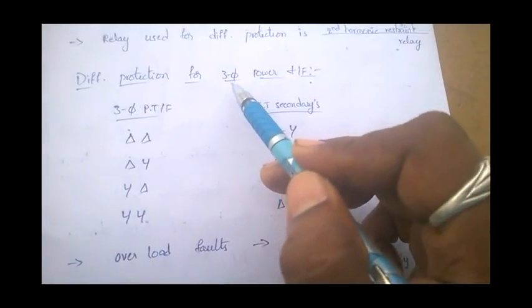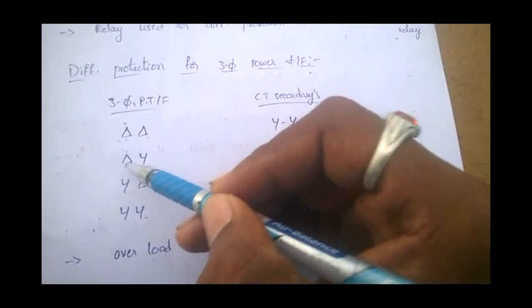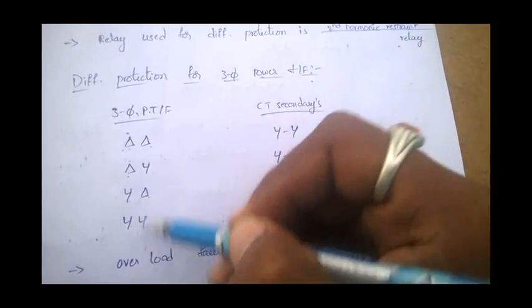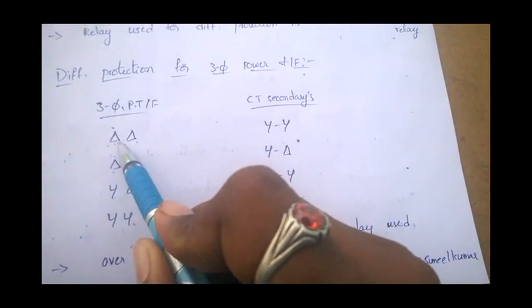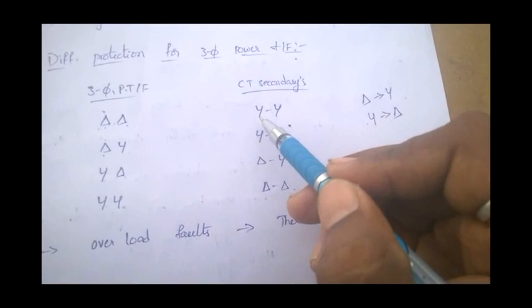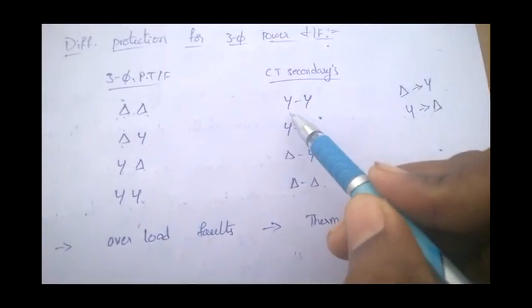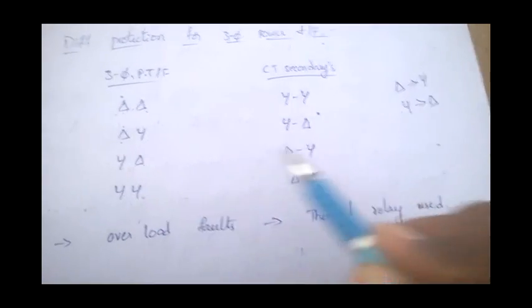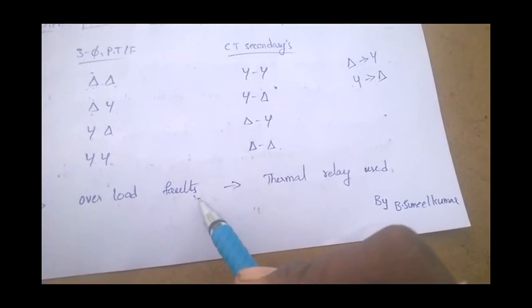For differential protection of a three-phase power transformer, the CT secondaries are connected in the opposite configuration to the transformer windings. That is, for delta winding, connect star-connected CTs; for star winding, connect delta-connected CTs. This opposite connection is used to protect three-phase power transformers. For overload faults in transformers, thermal relay is used.